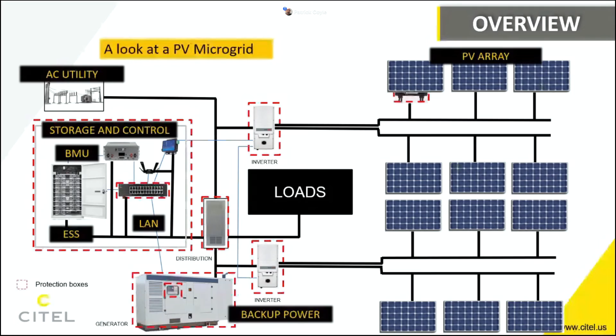So here we can put it all together and apply surge protectors to the microgrid application and get it protected. Since this is a PV microgrid, we can start with the PV array. So we'd place a PV SPD in the string, at the string combiner, in a junction box within the string, or it could even be at an OEM level, with surge protective components like a gas discharge tube or a varistor directly in equipment like the power optimizers that we said are using maximum power point tracking. Next, we can jump over to the inverter, and we can make sure that we place protection at the DC input. In this case, it has dual inputs. It also requires an AC SPD on the AC output, and we can't forget the communication lines. It can be either Ethernet or it can be an RS-485.